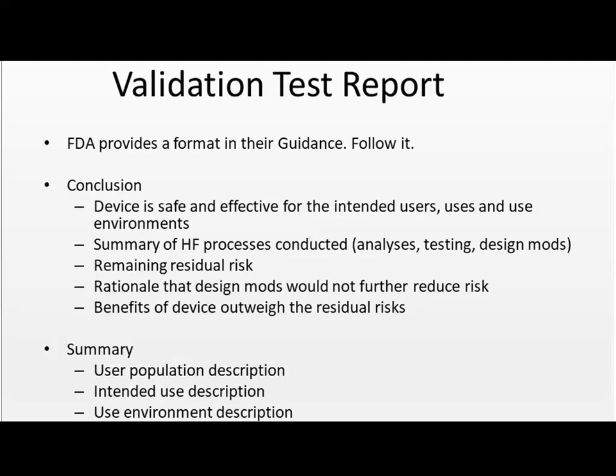At the end of the test and the analysis, you would create a test report. Now, a test report is mentioned both by the FDA and by IEC. IEC casually mentions they want a test report. FDA places great emphasis on a test report. It's very important to the FDA.